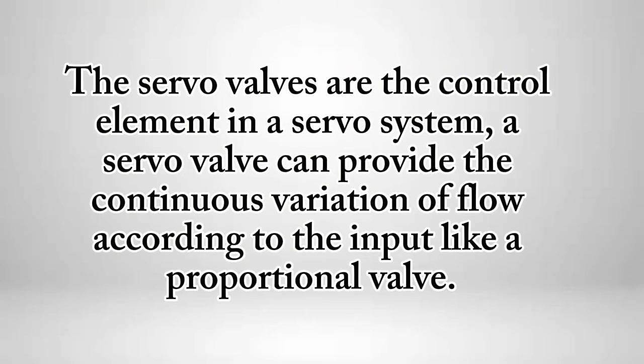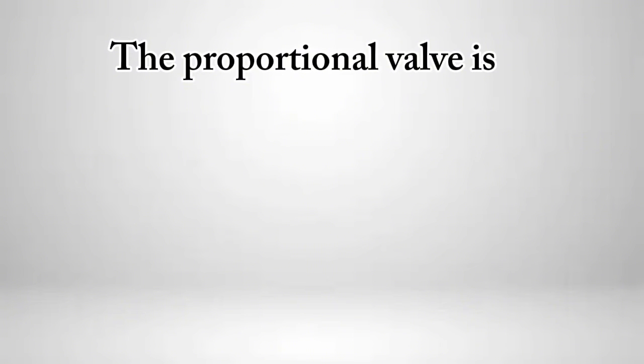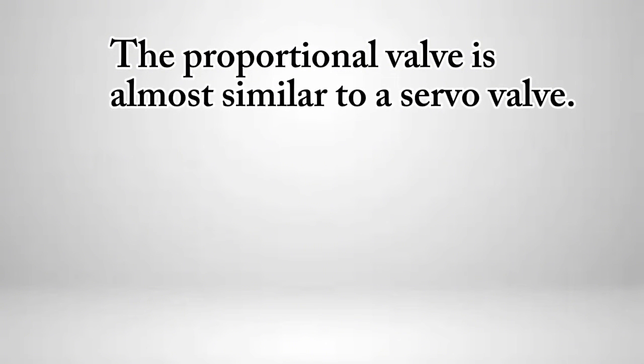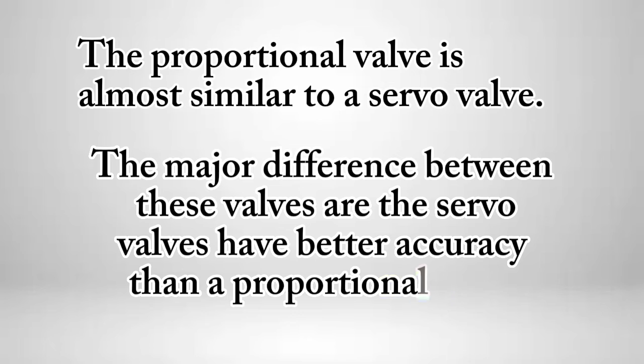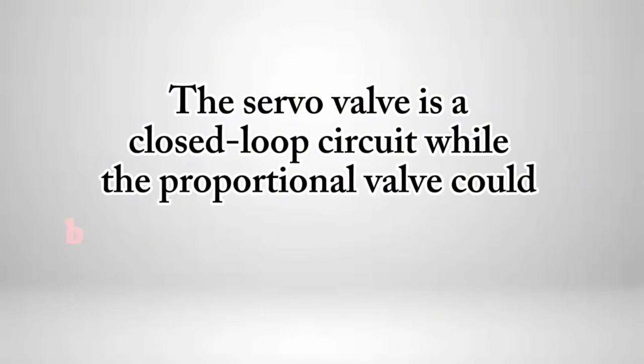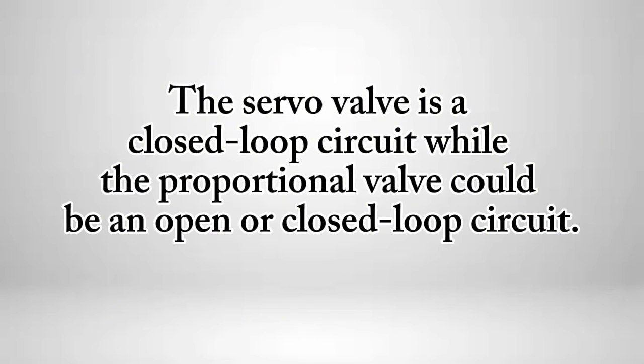A servo valve can provide the continuous variation of flow according to the input, like a proportional valve. The proportional valve is almost similar to a servo valve. The major difference between these valves is that servo valves have better accuracy than a proportional valve. The servo valve is a closed loop circuit, while the proportional valve could be an open or closed loop circuit.